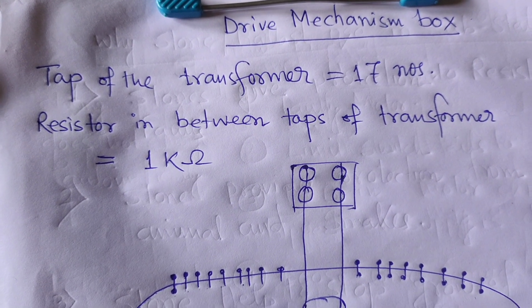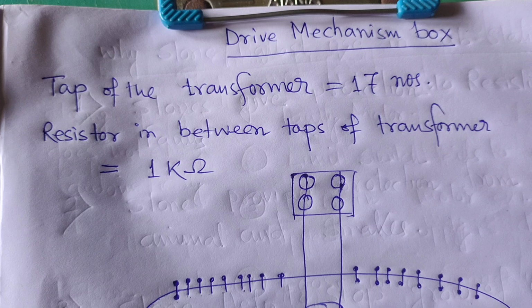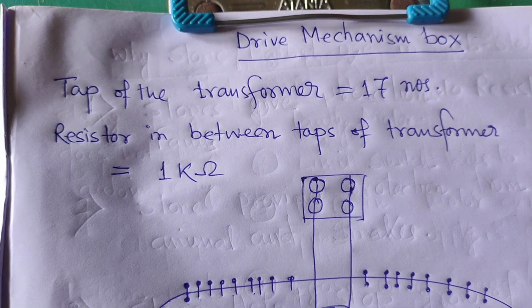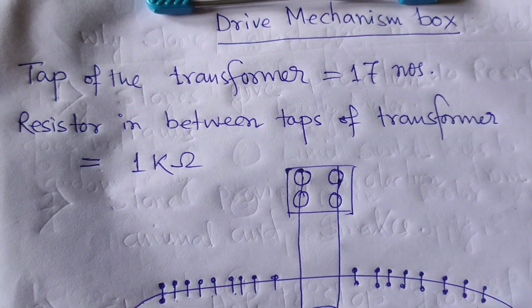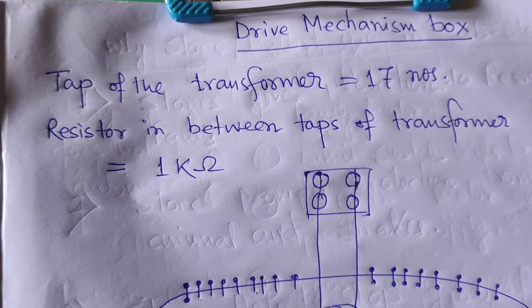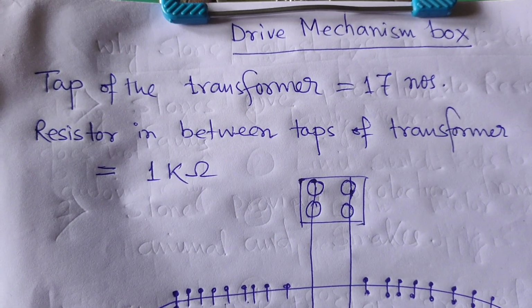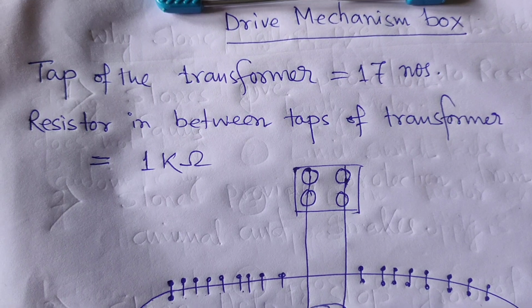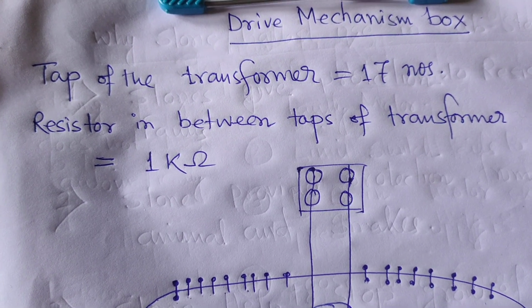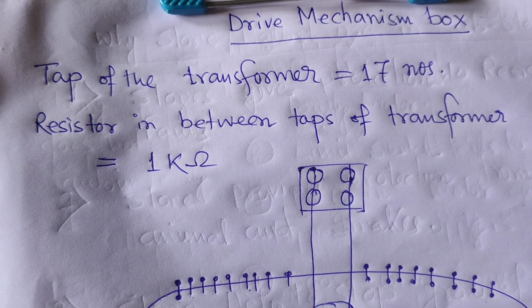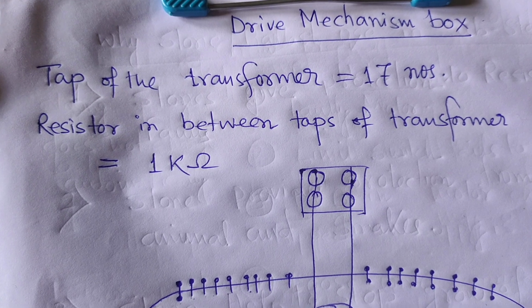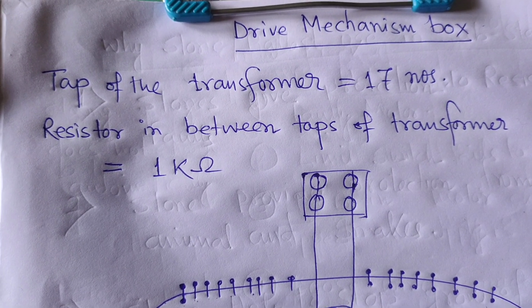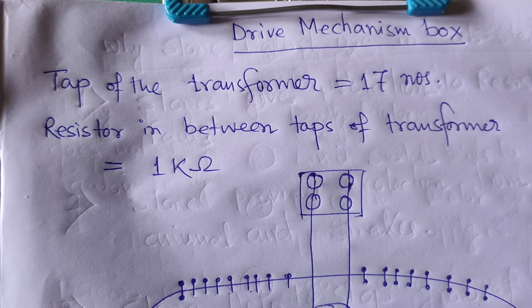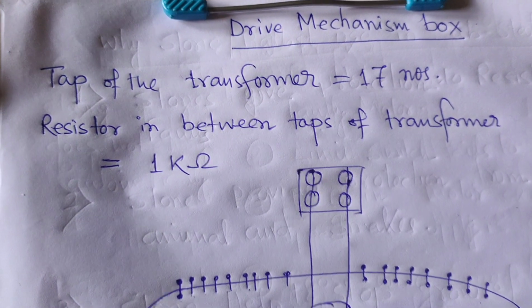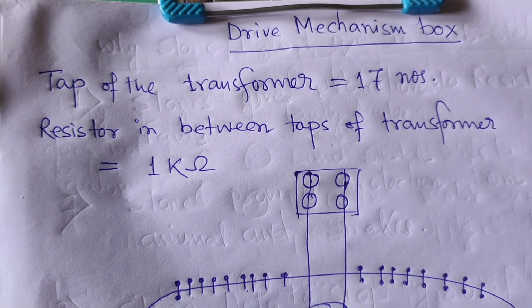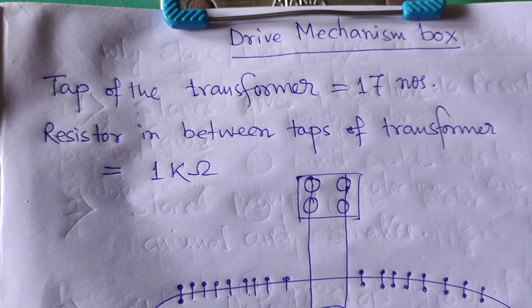It may be controlled by the load dispatch center or by the substation control engineers as per the requirement. If there is a requirement to change the tap to maintain balanced voltage and balanced frequency, we operate the tap from lower to higher according to the situation. Generally the transformers have a number of taps: 17.